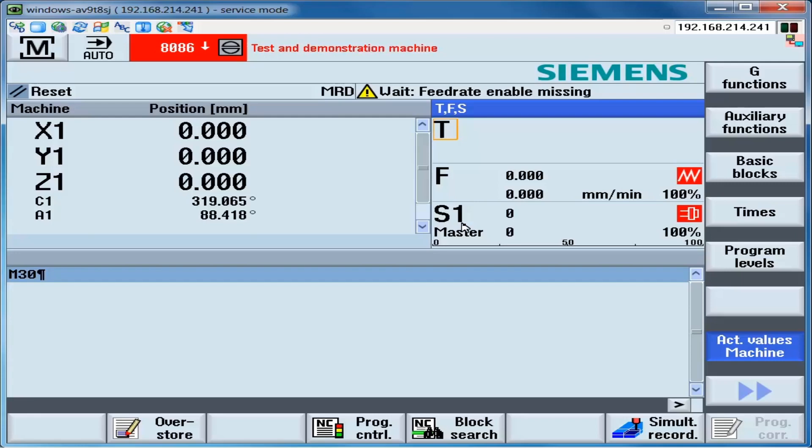However, in the case of separate rotor stator sets such as Siemens 1FE and 1FW rotary motors, 1FN linear motors, or third-party synchronous motors, the relevant measuring system is installed by the machine or spindle builder and is not necessarily synchronized.